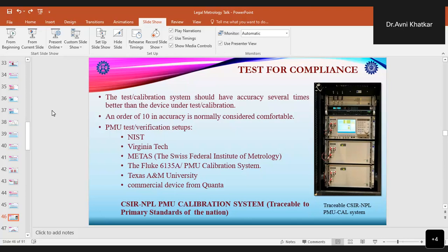However, the Fluke 6135A is a rack system. That is, it is on wheels, it can be purchased, and it can be used for testing in the field also. It is automated, and by automation and by traceability of this system, testing of PMUs can be done, requiring a testing time of around 6 to 12 hours per PMU. And at CSIR NPL, we have established this PMU calibration system, and it is traceable to the primary standards of the nation.